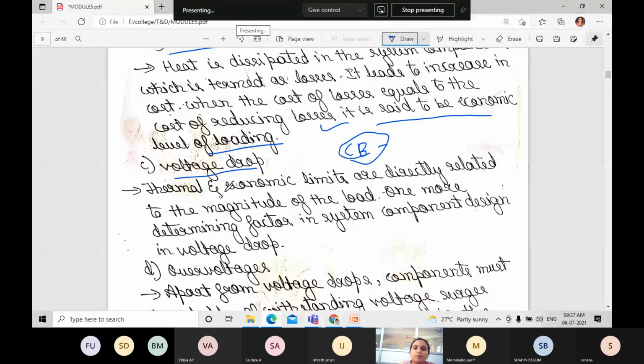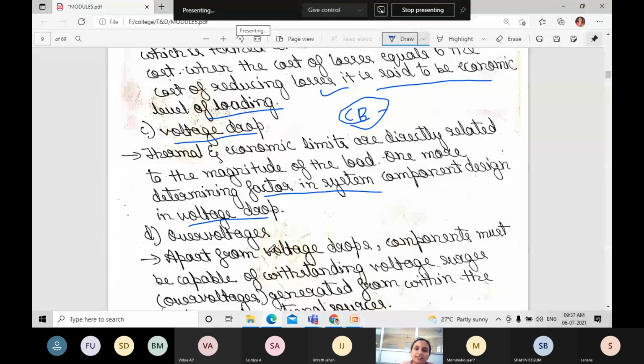Next is voltage drop. Thermal and economic limits are directly related to the magnitude of the load. But one more determining factor in system component design is voltage drop. For example, if you take any equipment or component, what voltage drop may occur? Whether it can withstand plus or minus, that is the tolerance.